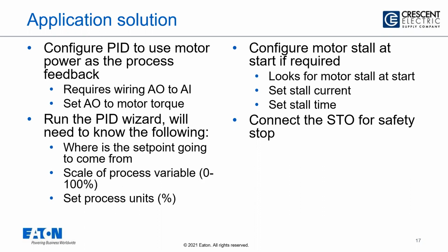And it is the PID wizard that helps you with an easy setup. It will even ask you where the set point is coming from. You can configure it, and what is the range of the process variable, whether it is 0 to 100% or in units, and set the process units in percentage, and then it automatically controls the motor speed, or the impeller speed, to make sure that the torque is constant.